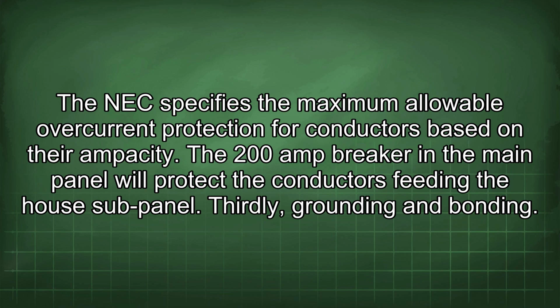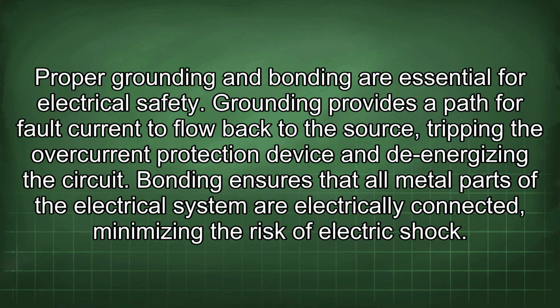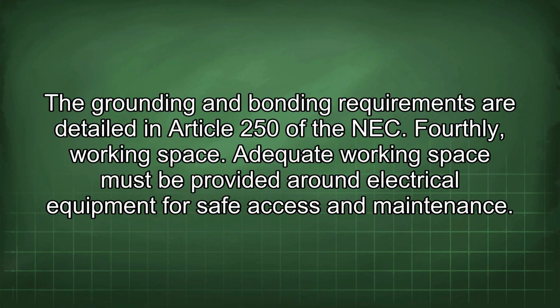Thirdly, grounding and bonding. Proper grounding and bonding are essential for electrical safety. Grounding provides a path for fault current to flow back to the source, tripping the overcurrent protection device and de-energizing the circuit. Bonding ensures that all metal parts of the electrical system are electrically connected, minimizing the risk of electric shock. The grounding and bonding requirements are detailed in Article 250 of the NEC.